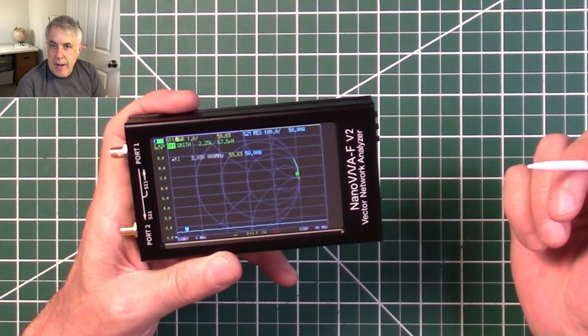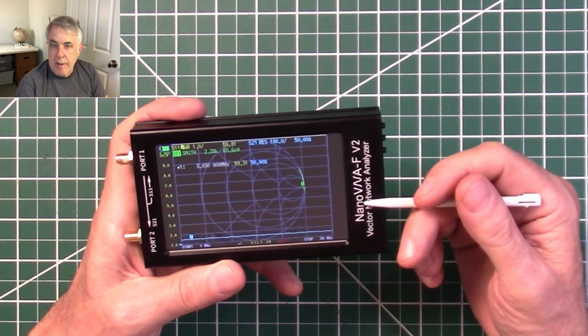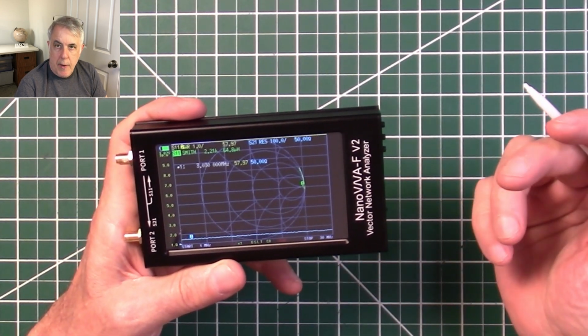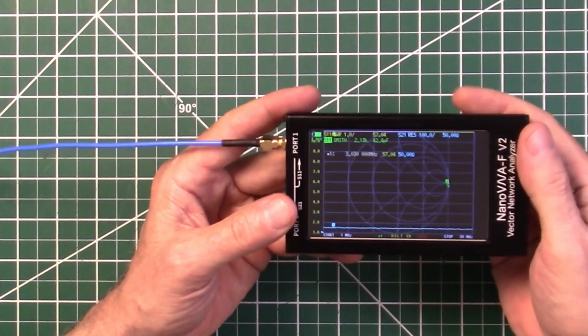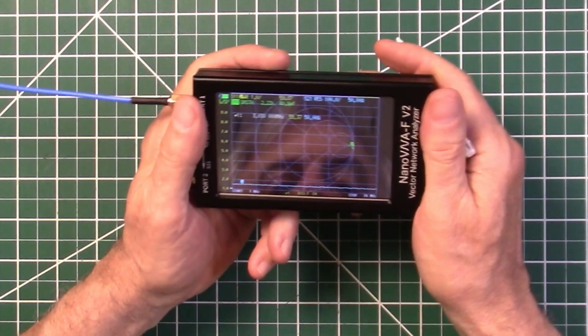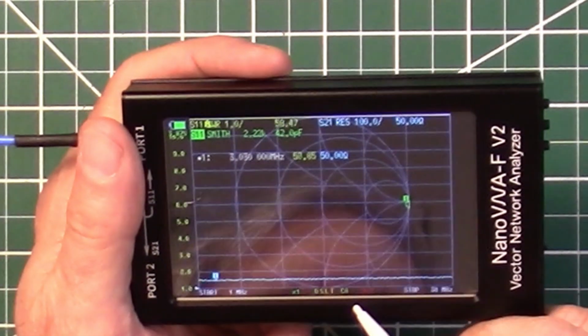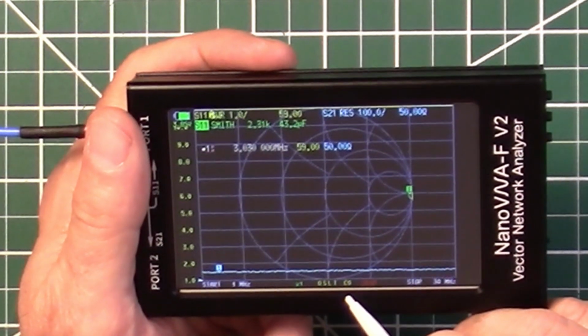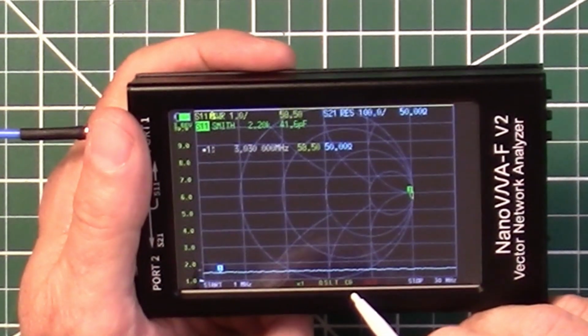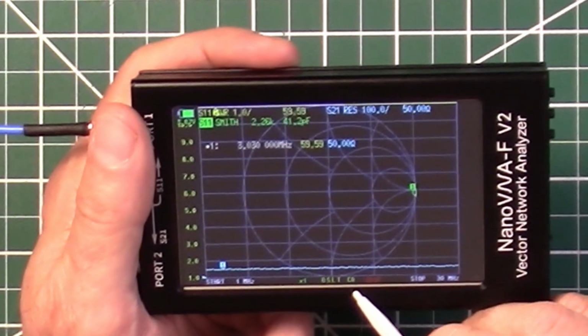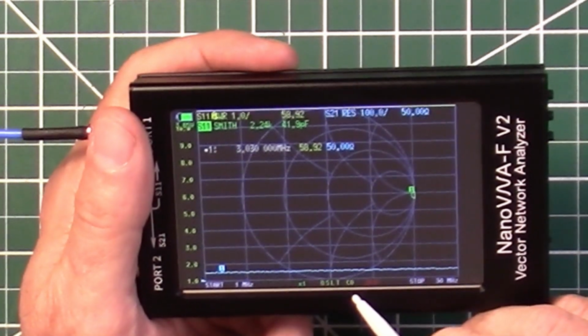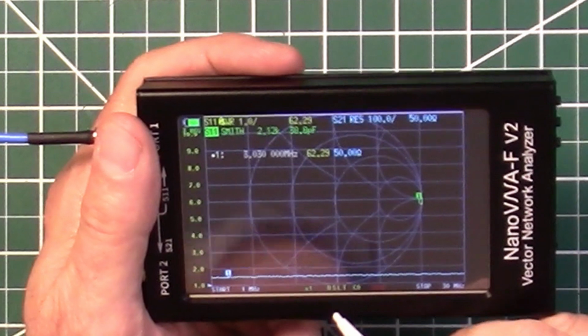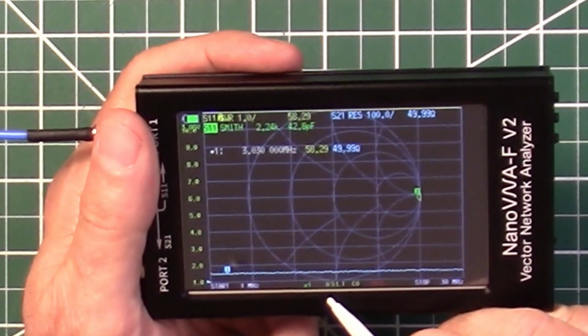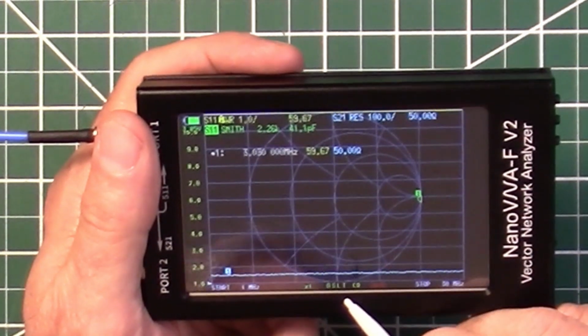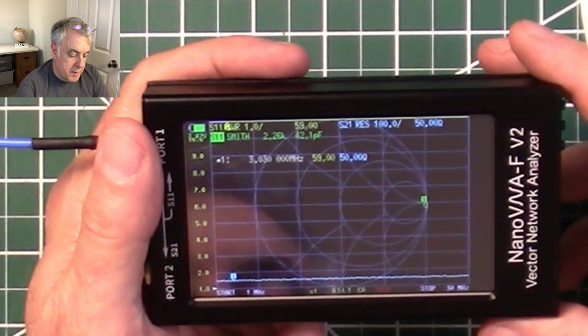And we'll get into the navigation on this a little bit. I found some things I like. I found some things that I don't like, and I'm going to share that with you. Let's go ahead and reconnect the cable. I calibrated the unit with the cable, and you can tell it's calibrated because right here, you see that capital C? That capital C, it says it's calibrated, and right now, if you see the 0 right there, it means I'm using a memory position 0. I loaded the calibration from memory position 0, and the OSLT means it's calibrated for open, short, load, and through, using the calibration devices that they sent with it.